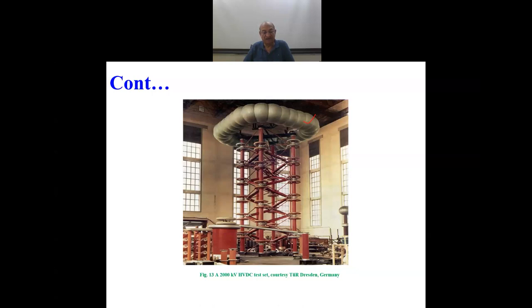As I mentioned, the requirement of DC generators is very specific. So all high voltage laboratories may not have a high voltage DC generator test set, but it is always desirable to have one. You may need DC to be applied one day, or you may need mobile test units. And in the physics departments, you would see the particle accelerator, the Van de Graaff generator. That has a completely different principle, let me tell you. The Van de Graaff generator, the electrostatic charge accumulation system, does not have this kind of voltage doubler circuit. The principle is completely different. So this is a continuous DC output by the high voltage DC test generator.